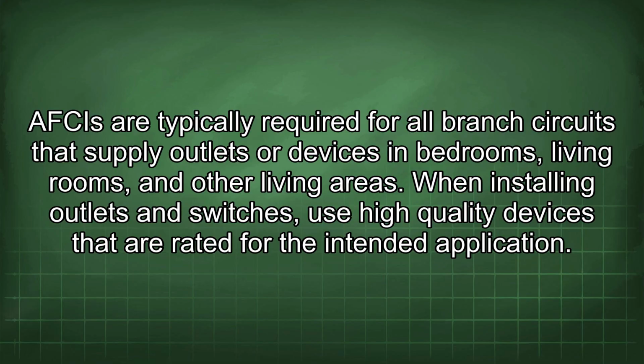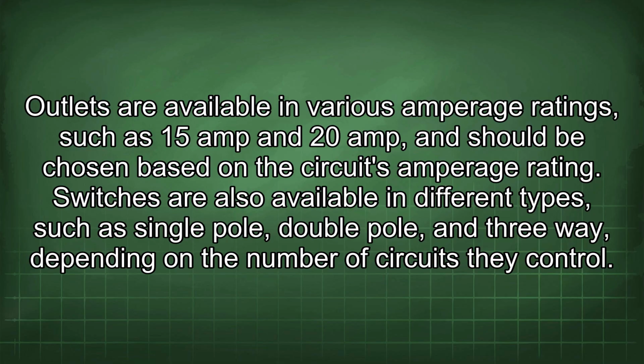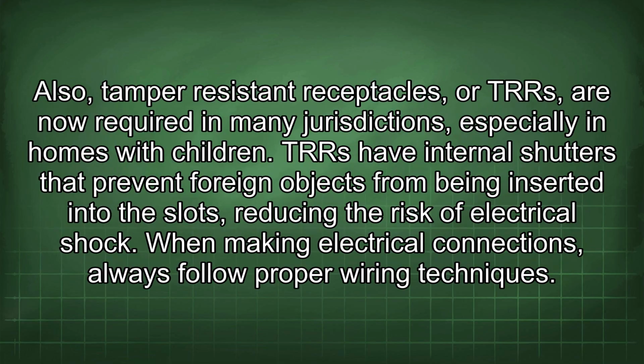When installing outlets and switches, use high-quality devices that are rated for the intended application. Outlets are available in various amperage ratings, such as 15 amp and 20 amp, and should be chosen based on the circuit's amperage rating. Switches are also available in different types, such as single pole, double pole, and three-way, depending on the number of circuits they control. Also, tamper-resistant receptacles, or TRRs, are now required in many jurisdictions, especially in homes with children. TRRs have internal shutters that prevent foreign objects from being inserted into the slots, reducing the risk of electrical shock.